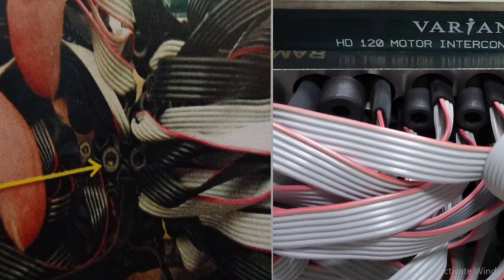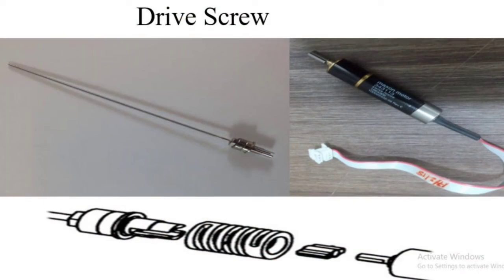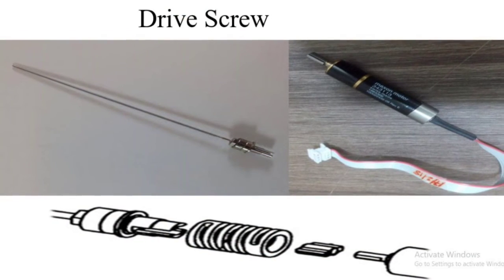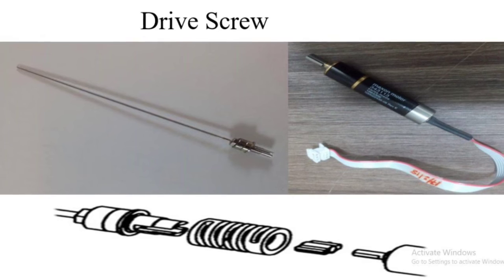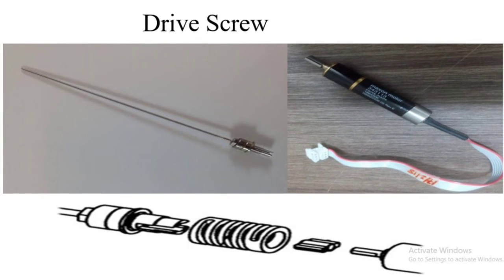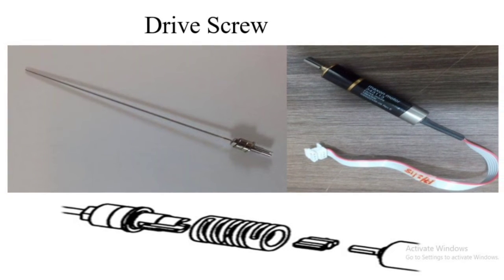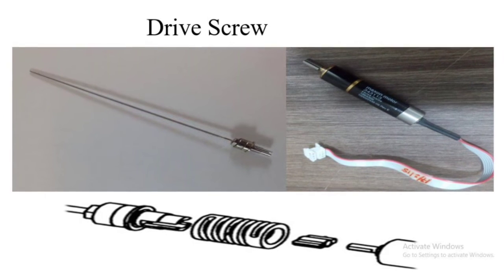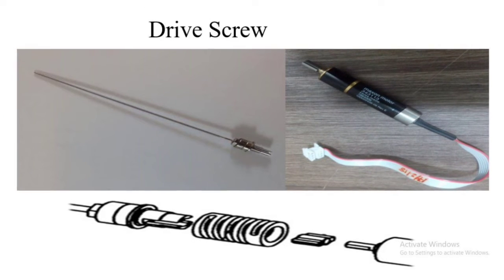Setting the new motor, you have to feel the spring. That means the MLC motor is properly fitted with the drive screw. After that, put back the screw, connect the new motor to the panel and put back the MLC cover. Now switch on the MLC power supply and try to manually move the same MLC. It should work. Then you have to do MLC calibration.